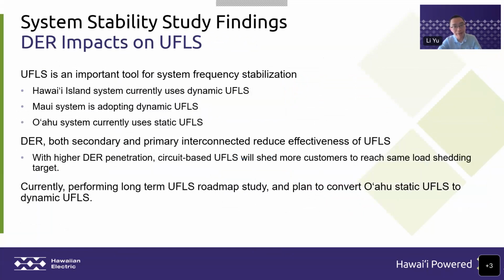With higher and higher penetration of DER on our distribution side, we also see that it starts to reduce the effectiveness of our underfrequency load shedding system. The underfrequency load shedding system is still a really important tool for our system to stabilize the frequency as a last resort. To address that issue, the Hawaii Island system is currently using dynamic underfrequency load shedding, which actively looks at the available net load in the system that can be used for load shedding to stabilize frequency. Also, in our Maui Island system, we are adopting dynamic underfrequency load shedding right now. And for the Oahu system, so far we're still using a static underfrequency load shedding system.